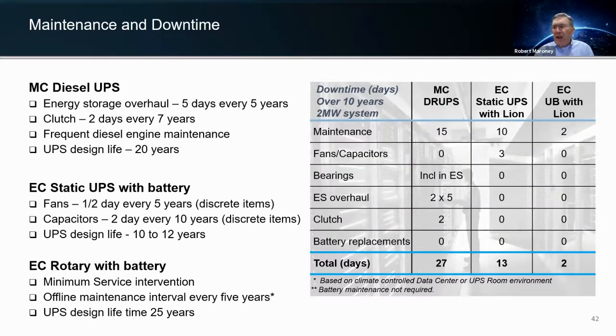Let's talk about maintenance and downtime on the 3 types of UPS systems we have out there. When you do a mechanically connected UPS, a big rotary machine, over a period of 20 years you're going to have over 15 critical maintenance events. When you look at electrically coupled static UPS, likely 2 a year, or at least one a year, you're going to have somewhere on the order of 10 main maintenance intervals. With a rotary UPS, you're only looking at 2, okay? So when you get to the bottom line, total days of downtime for maintenance on these 3 different types of UPS topologies, you can go from as high as 27 over that 20-year period to as low as just 2, depending upon what your real maintenance events look like over the life of the systems.